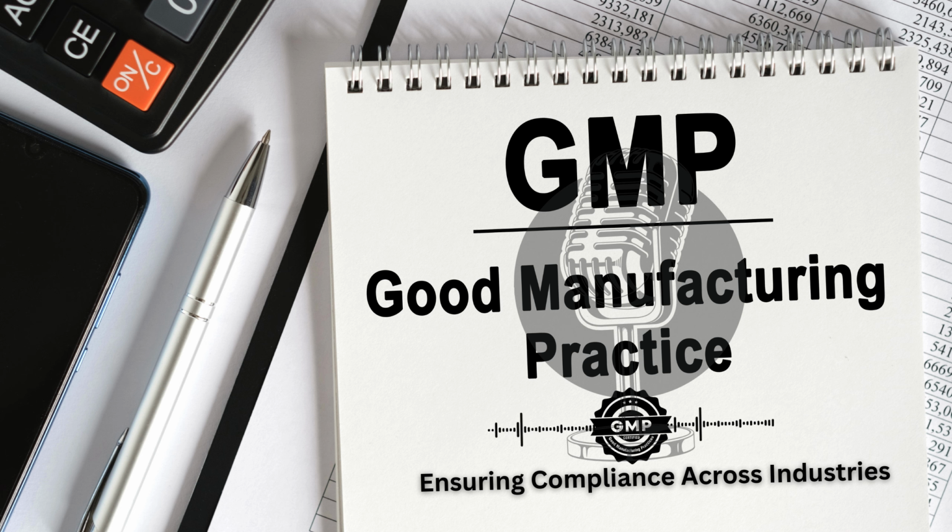Makes sense. Another important update involves the sterilization of medical devices using ethylene oxide. Okay. Ethylene oxide is a really critical method for sterilizing certain types of medical devices, particularly Class 3 devices, which, just to clarify, are the highest risk category of medical devices. The FDA has issued a transitional enforcement policy here. This policy provides new guidelines to help manufacturers who rely on ethylene oxide sterilization to transition towards potentially safer sterilization alternatives, while also working to maintain the stability of the medical device supply chain.